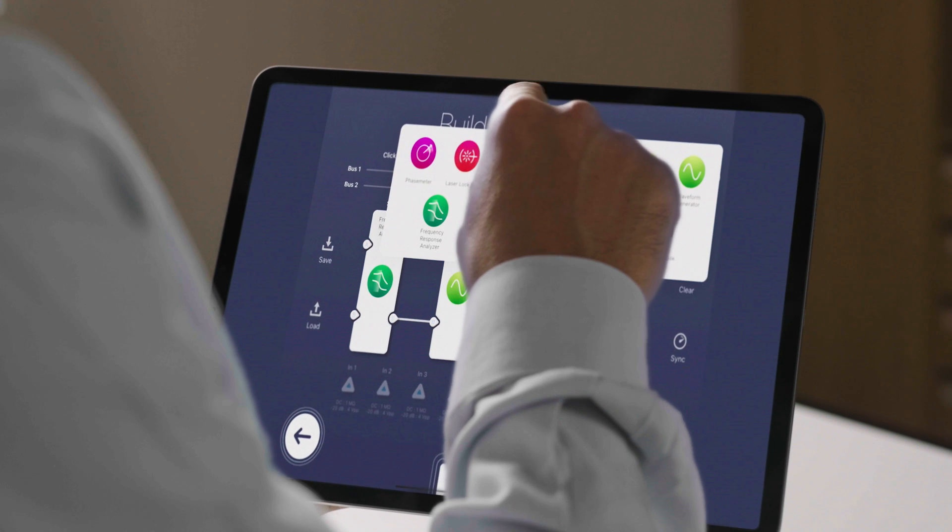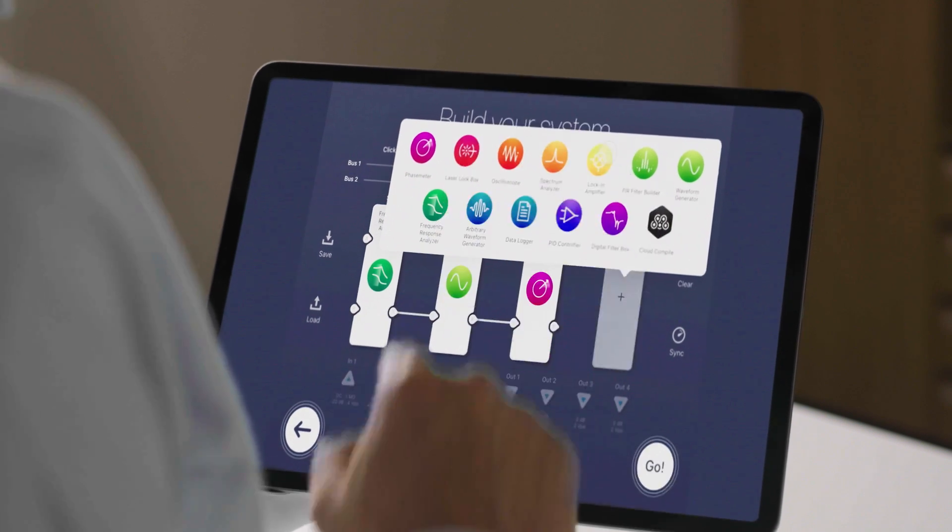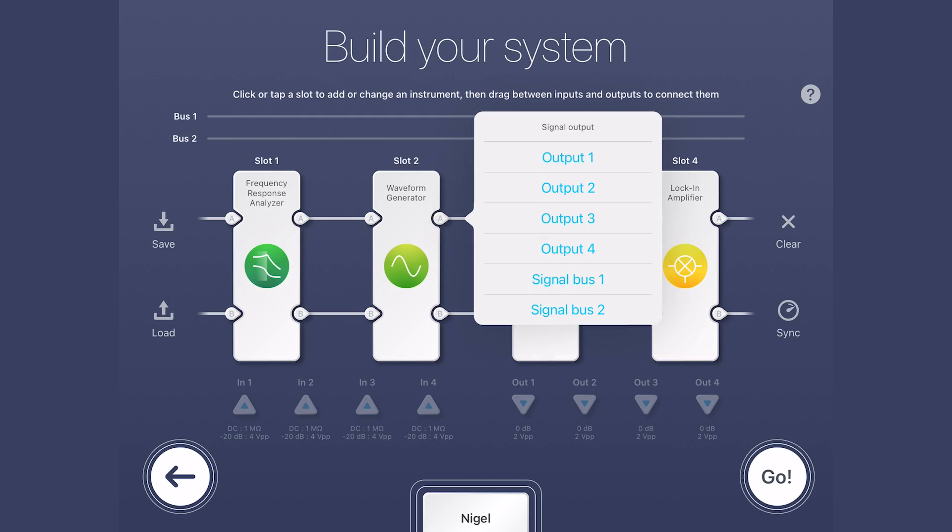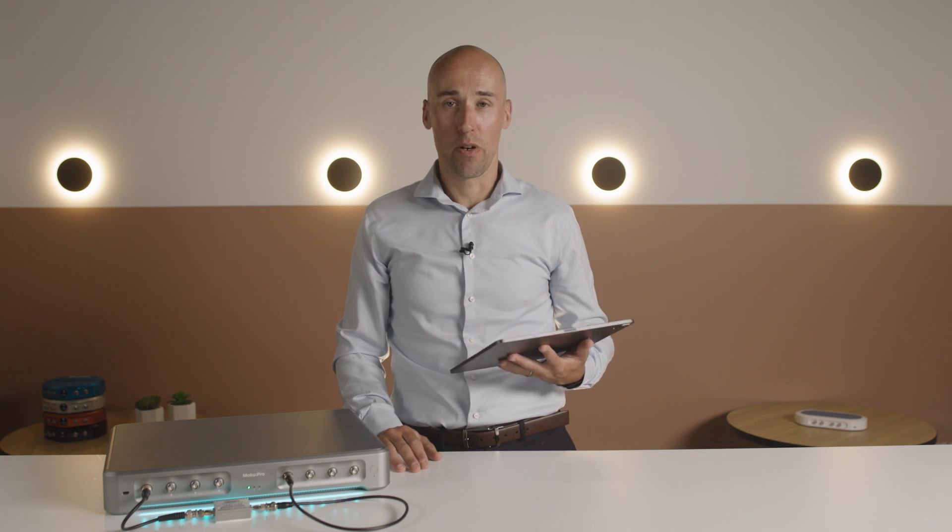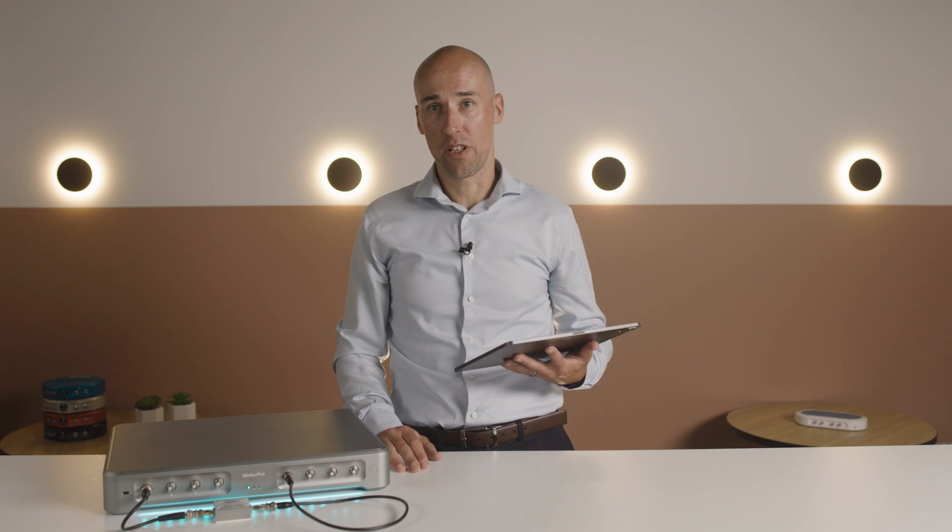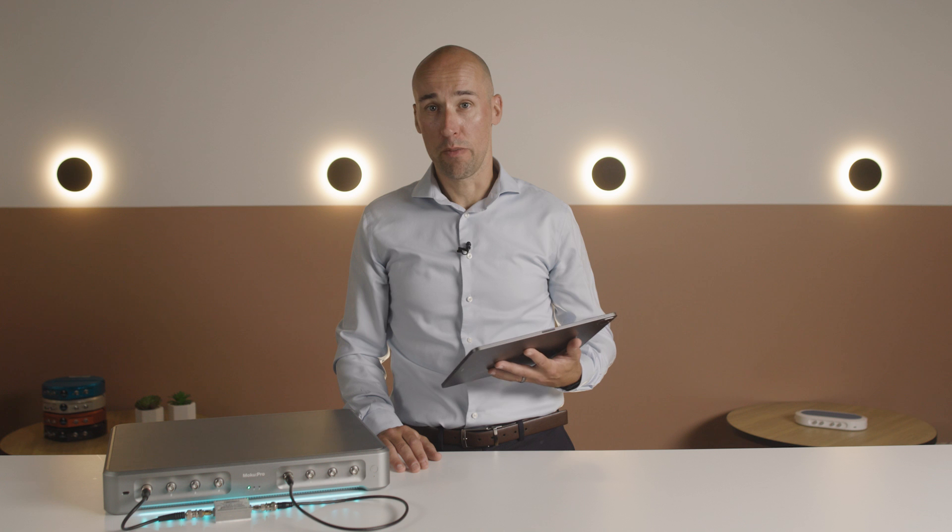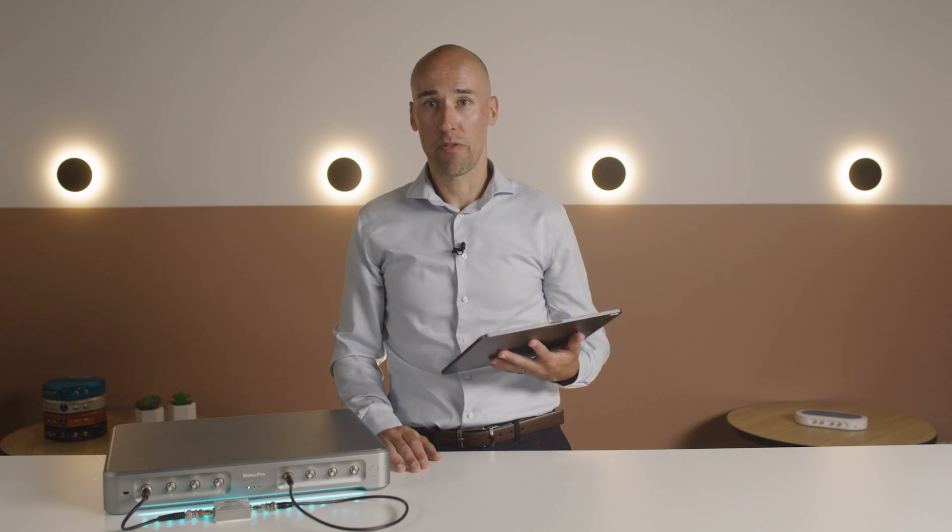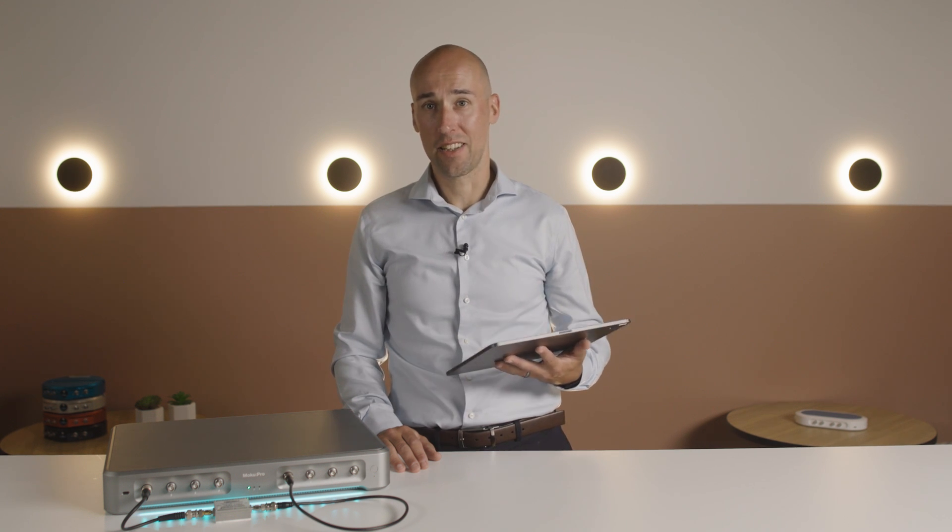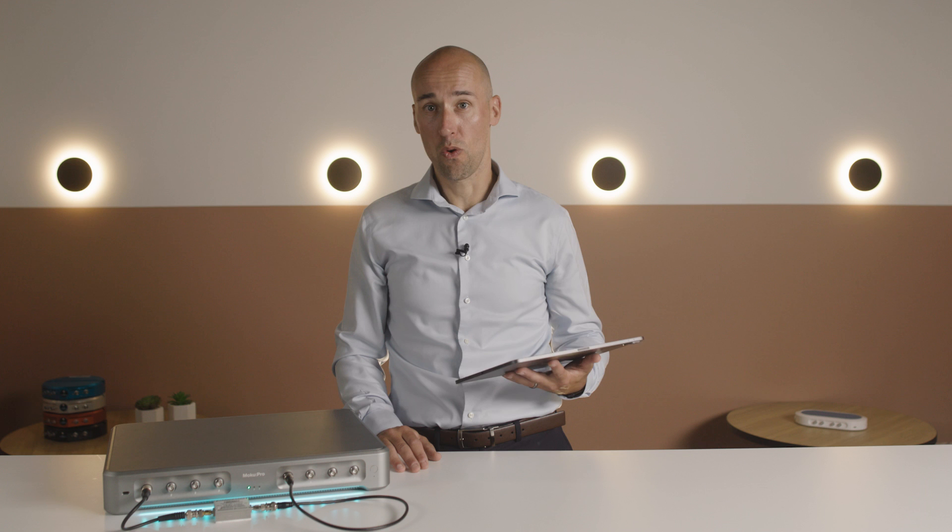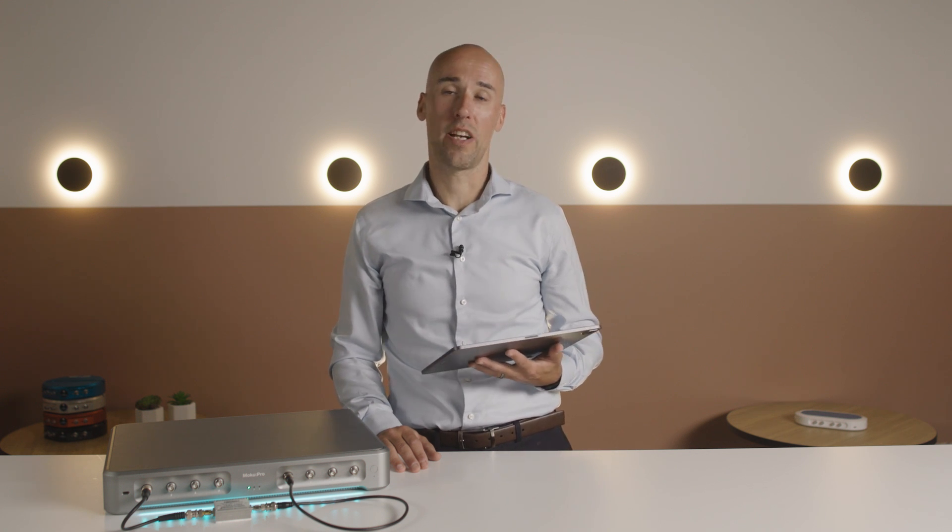Here, the waveform generator phase modulates the input of the device under test and the lock-in amplifier demodulates its output. There's a lot more you can do with the Moku Pro Frequency Response Analyzer, including using multi-instrument mode to string together up to four instruments at a time to add additional filters or characterize another instrument in the signal chain.